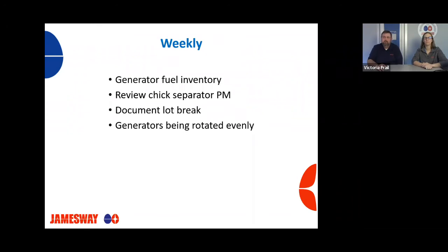Weekly, check generator fuel level. Review the chick separator, preventive maintenance where you watch if chicks are getting lost. Document your lot breakout. If you're at a facility that has 2 generators, I like for those generators to be alternated from week to week. That way you keep the hours more even. We really look for you to do the same thing, especially on your water pumps. If you have 2 water supply pumps, particularly in single stage, do be switching over monthly from one to the other. That way, in case one does go down, you know that the other one is still operational. Right, I agree.